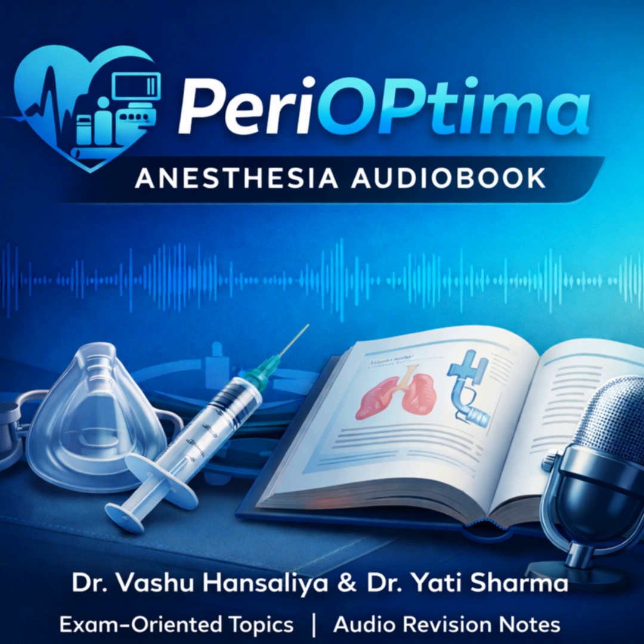Two big reasons. First, as we said, to prevent silent depletion if the pipeline pressure fluctuates. But second, if the pipeline fails during the case, you want the low-pressure alarm to sound so you know there is a problem. If the cylinder is left open, it just seamlessly takes over, empties itself without you noticing, and then you have a double failure with no backup. Got it. Okay, step 2?